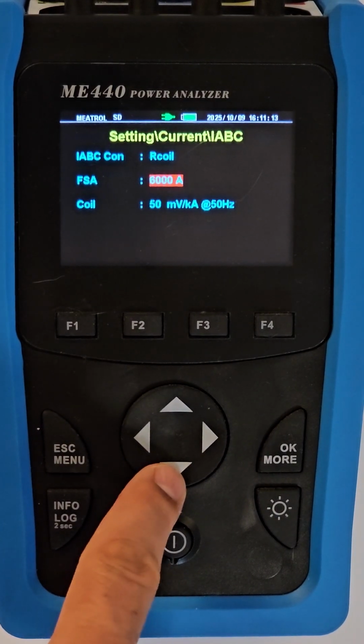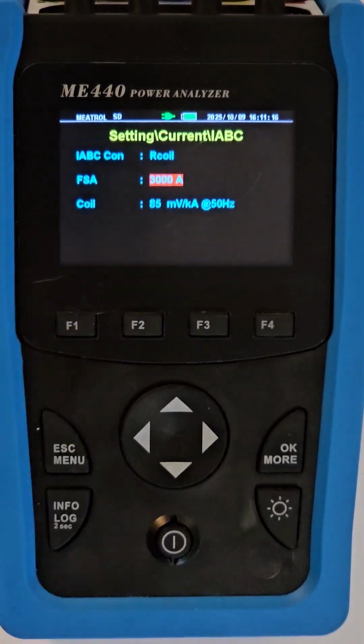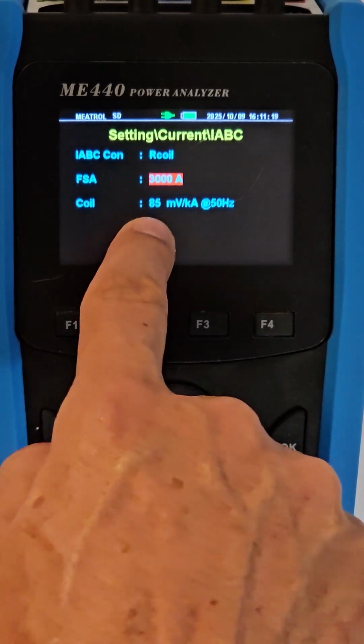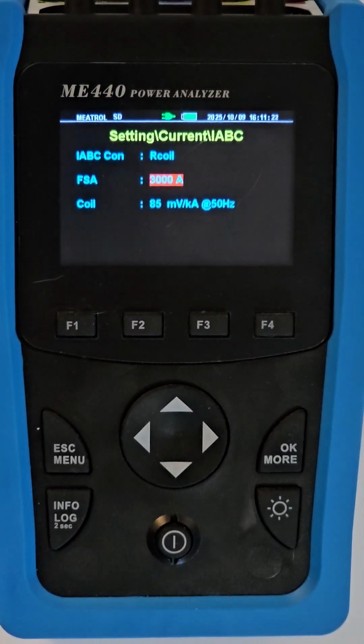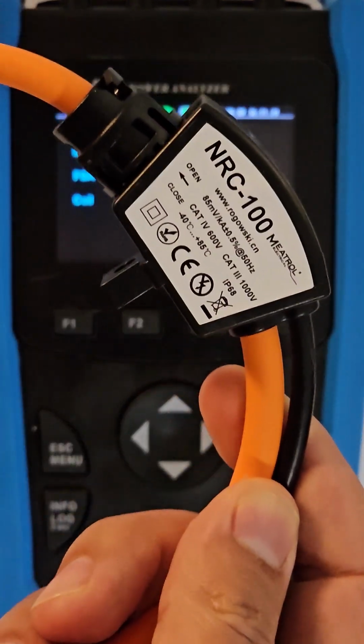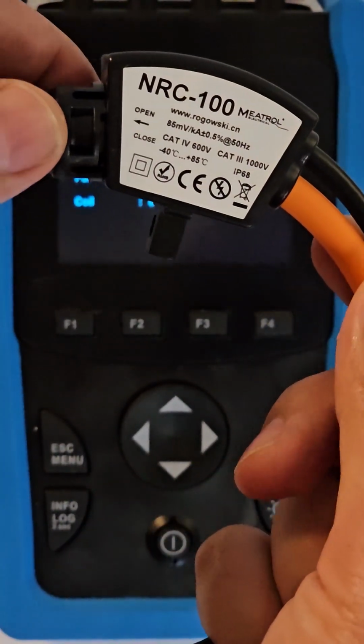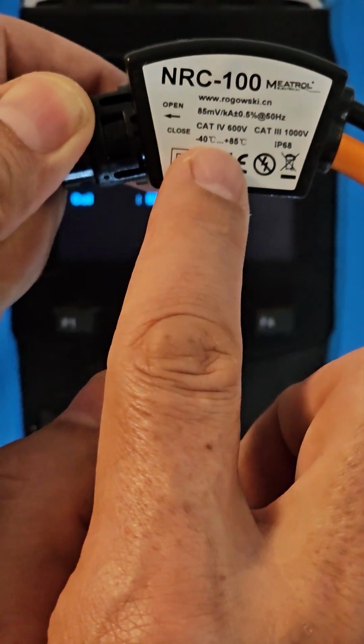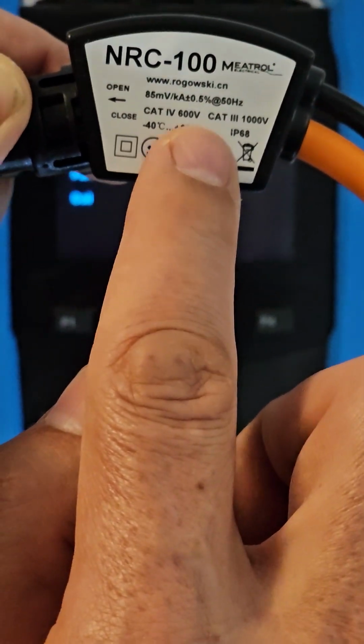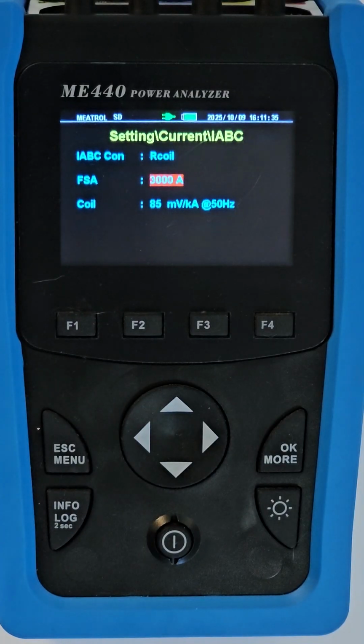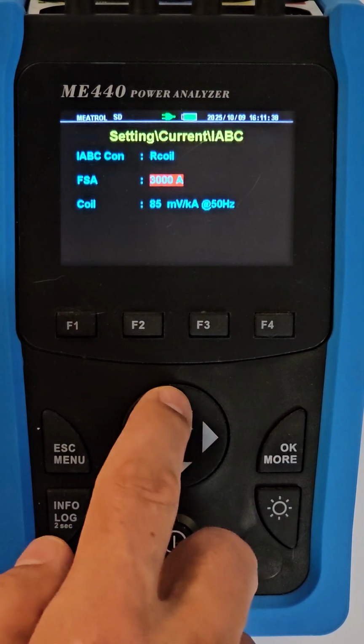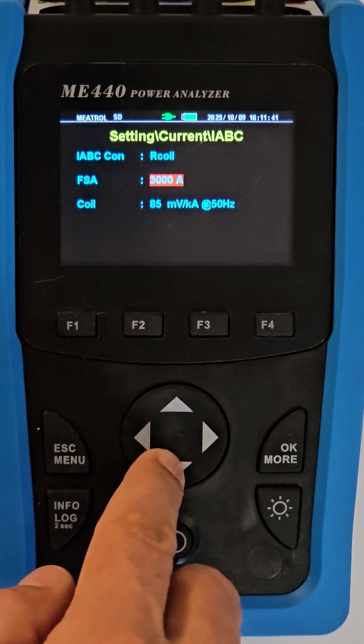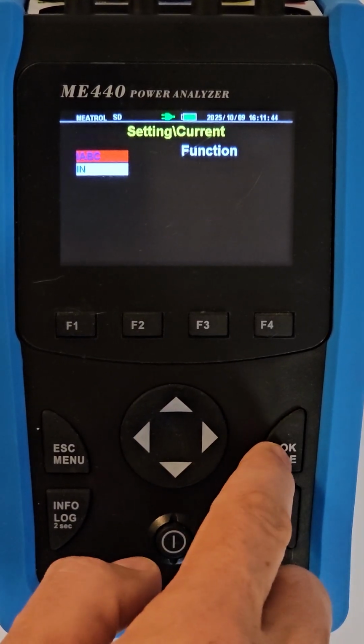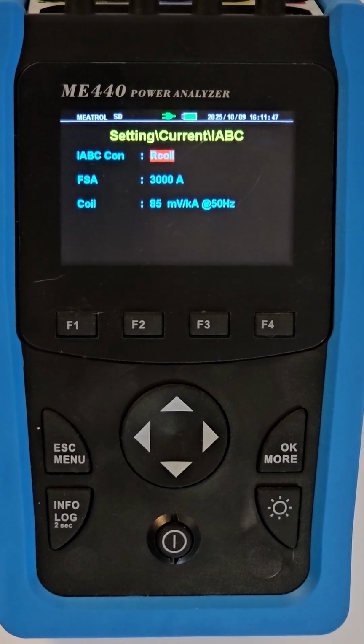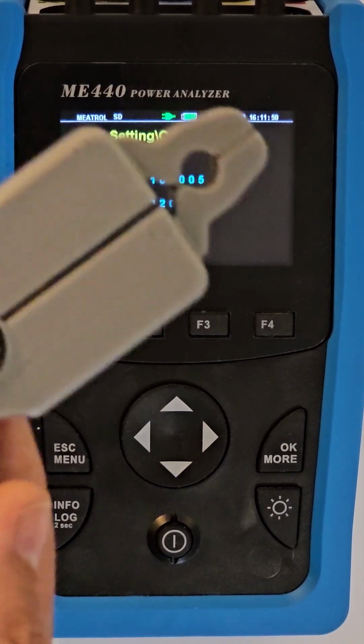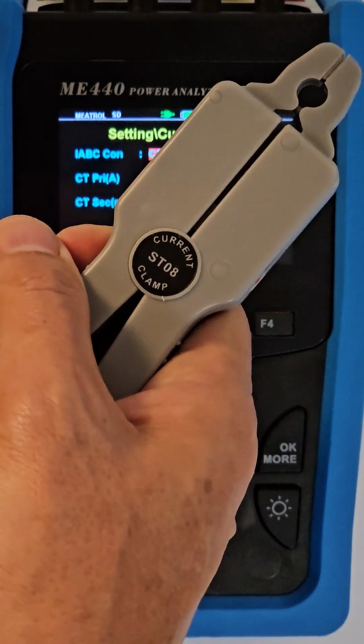And if we change it to 3000 amperes, you'll see the sensitivity change from 50 to 85 millivolts per kiloampere. That you'll use with the NRC 100 coils. That's got a sensitivity of 85 millivolts per kiloampere. Okay, so leave that there. And just to illustrate the CT settings, you'll use that for these ST08 current clamps.